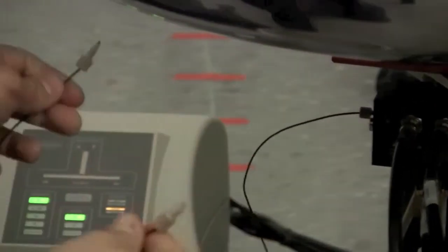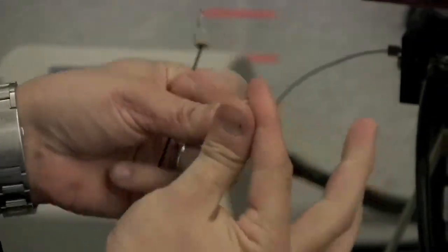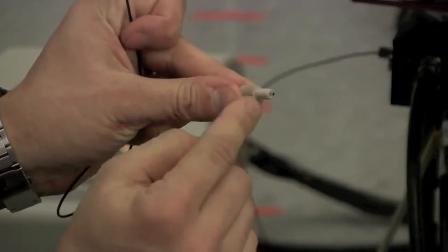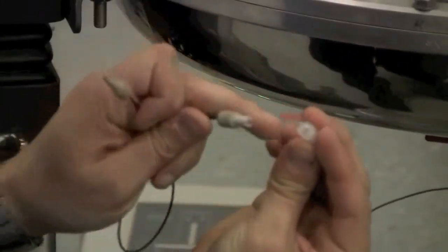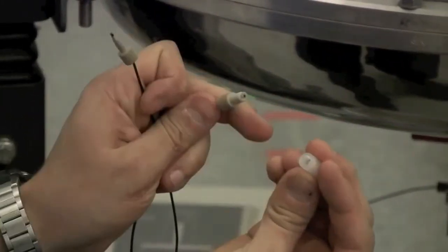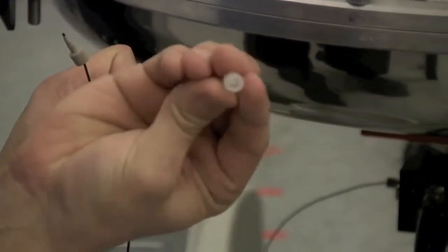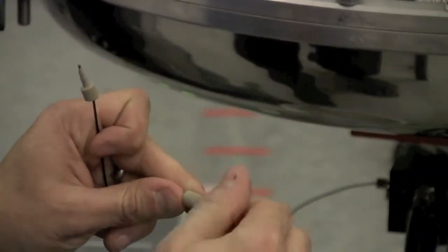And then I'm going to attach this next line here. This one looks almost like the other one, except that one side has the angled connection and the other side has a flat fitting on it. The reason for this flat fitting is that it is going to attach to the filter. So this white piece here is the filter, and inside there is a stainless steel filter with a little Teflon gasket. We're going to put the Teflon gasket up against the flat end here and tighten it down. So this is a filter on the inlet, and then this part is going to attach to the input of the probe.